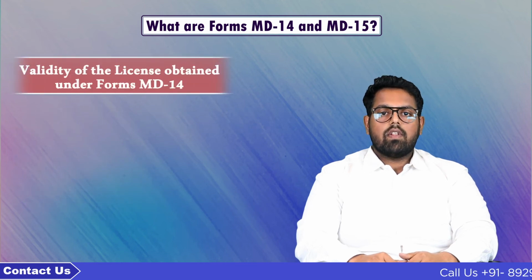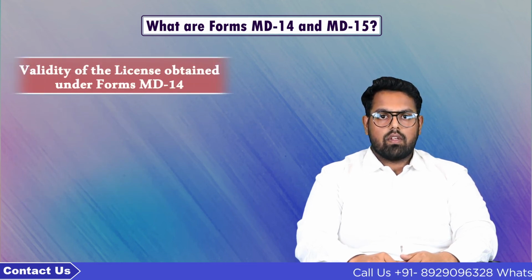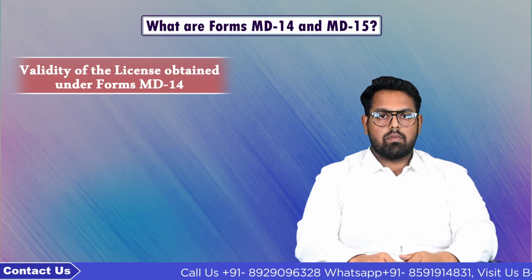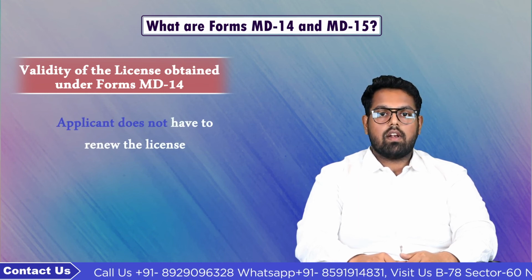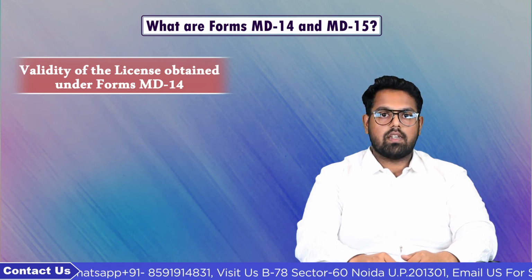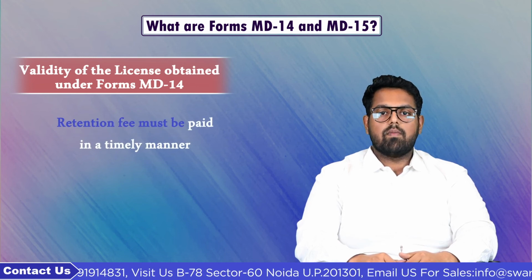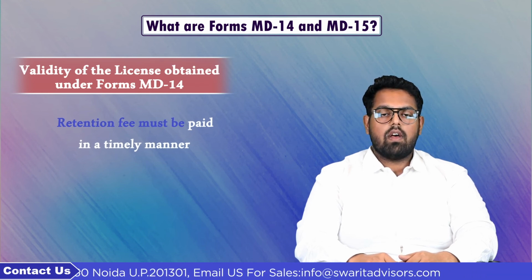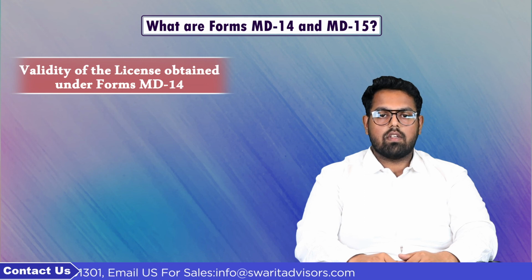What is the validity of the license obtained under Form MD-15? The validity of the license issued in Form MD-15 is perpetual. The applicant need not renew the license as long as the retention fee is being paid as per the norms stated in the second schedule. The retention fee must be paid in a timely manner in a span of 5 years from the date of issue unless the Central Licensing Authority revokes it.